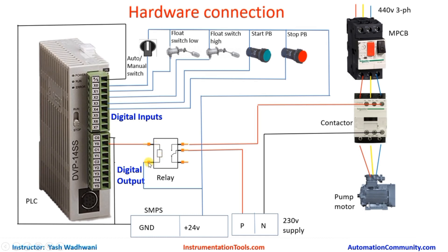The other terminal of the relay we connect to 24V supply. On the output side of the relay, we give the phase to the common of the relay, and the NO contact of the relay we connect to A1 of the contactor. A2 of the contactor we connect to neutral. So when Y0 is ON, the relay will be ON, the NO terminal will close, power will flow from phase through common to NO to A1 of the contactor, and the motor will operate.